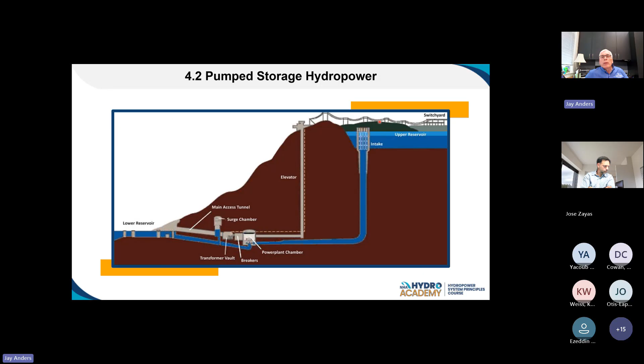We have this access hatch, this access tunnel, which gives us the way to drive vehicles in, bringing all the equipment down in here. Our transformers, our generator breakers are all down inside. At a lot of these plants, they'll have the transformer inside. They'll generate in the 20,000 volt range, and step it up to maybe 161,000 volts to take it to the top of the mountain. And because these are such large facilities, many times it'll get stepped up to the multi-100,000 volt range, sometimes up to 500,000 volts in the switch yard at the top of the mountain.